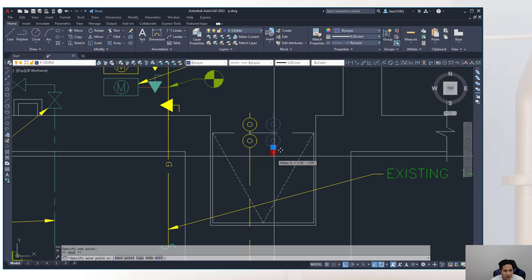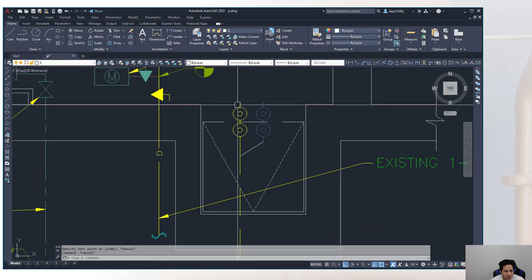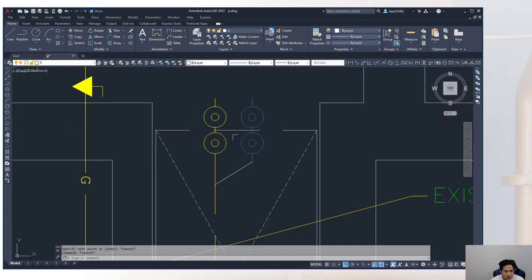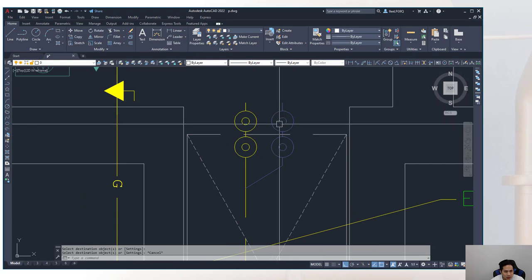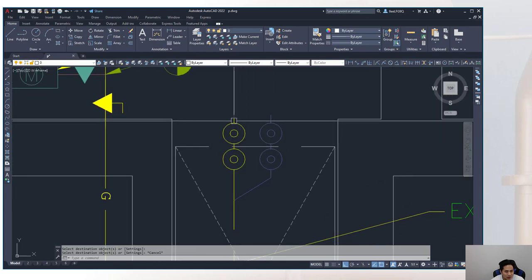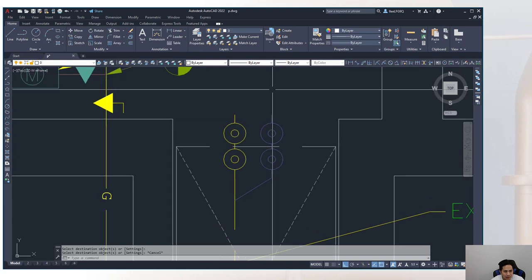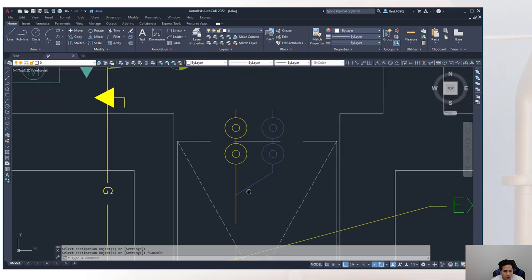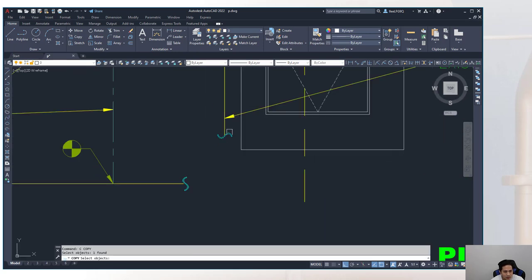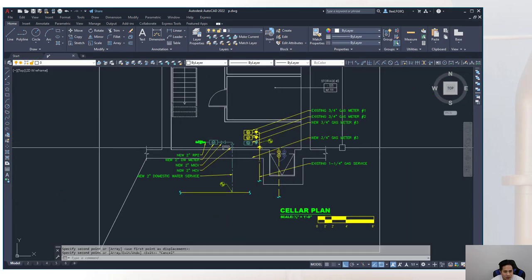For the laundry washers, a drain is needed — shown as a laundry standpipe using a funnel drain symbol above the floor. The circle in the symbol is not broken because it represents the opening to the funnel drain. Place the symbol on the P-waste layer since it is above ground. Show drains for both washers. Then pipe them to the underground waste piping using a pipe-down symbol — a break in the line where the above-ground pipe transitions to underground.